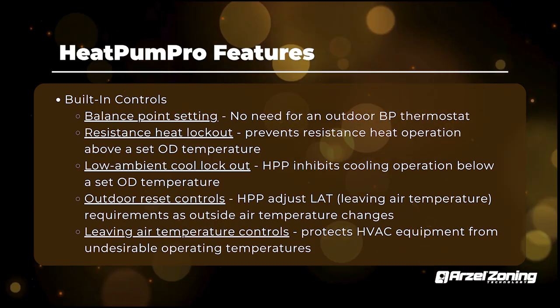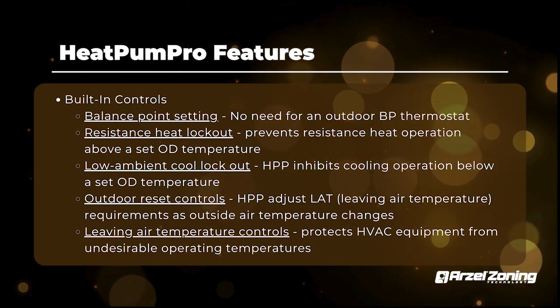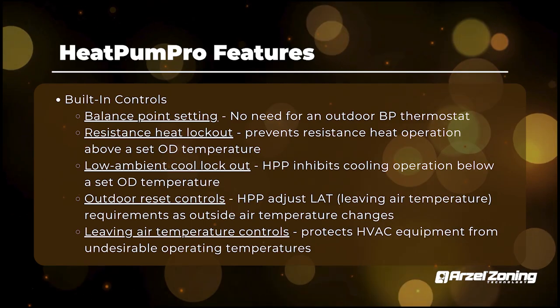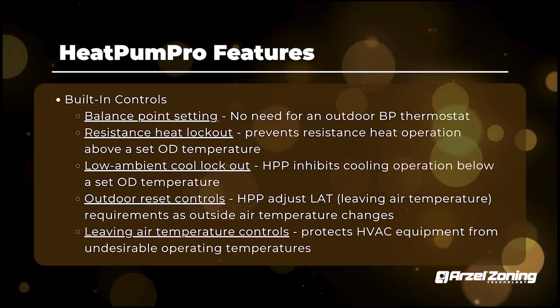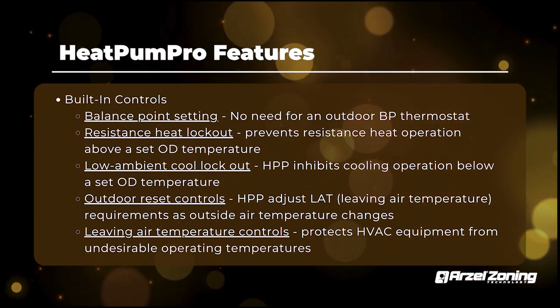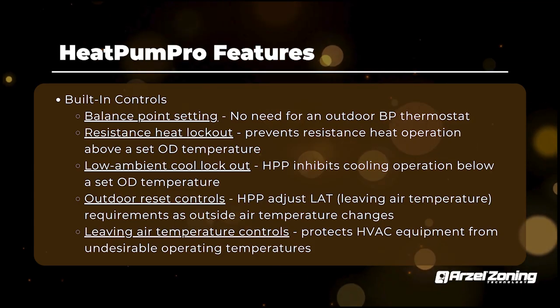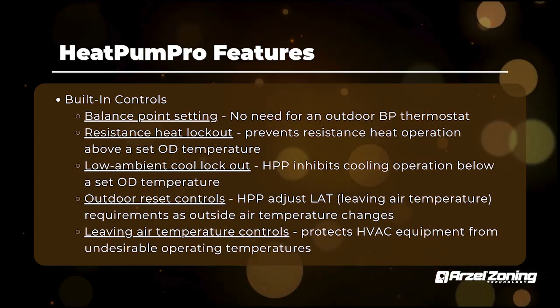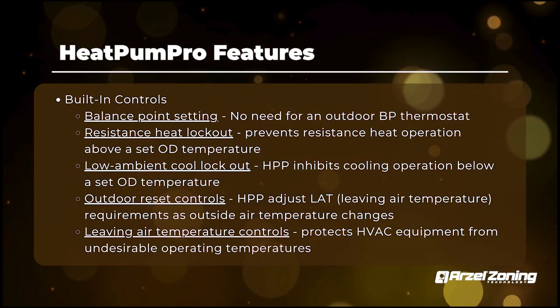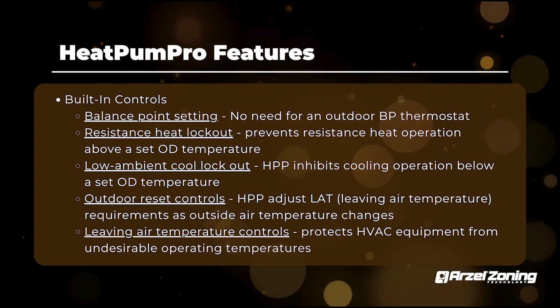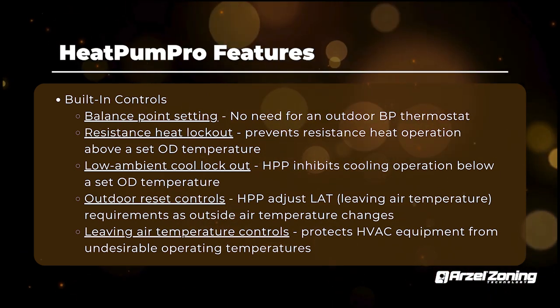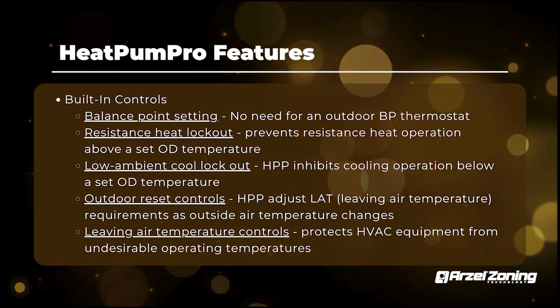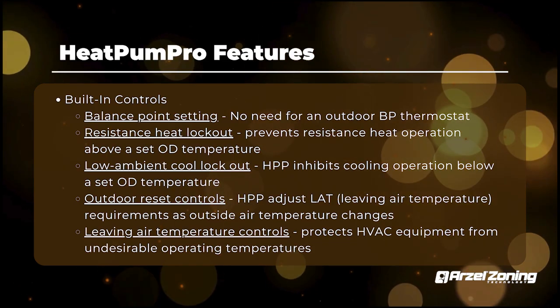It's also going to have outdoor reset controls. So as your temperature drops outside under 30 degrees, the panel itself is going to start staging more aggressively, just like your typical thermostat would. So it's a nice added feature. It keeps an eye on that outdoor temperature. And as those conditions start to worsen, your equipment's going to engage and stage up more aggressively to maintain that temperature in the home. It's also going to cover your leaving air temperature controls.